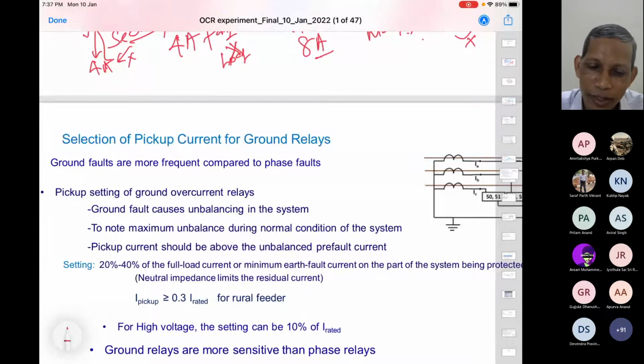So I asked you to consider the corresponding settings, and they say that they are very high settings. A very high setting means that many faults will not be detected. So, as a compromise, from the perspective of operational performance of your system, you have to consider the life of the particular transformer or device. That is what the pickup setting is.